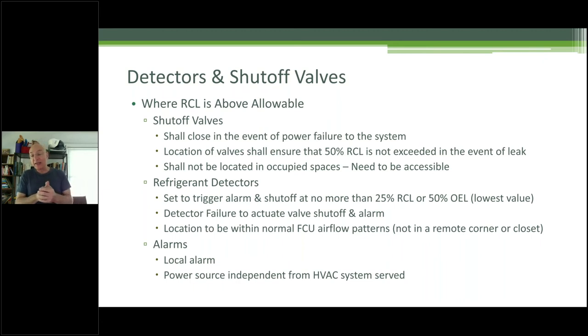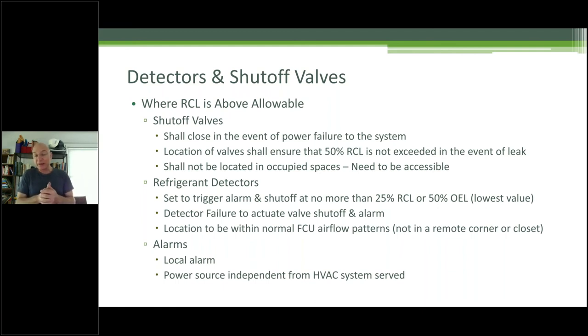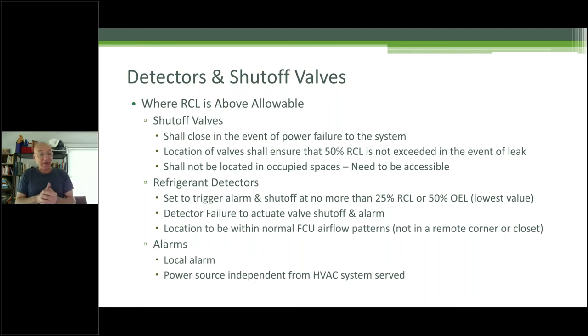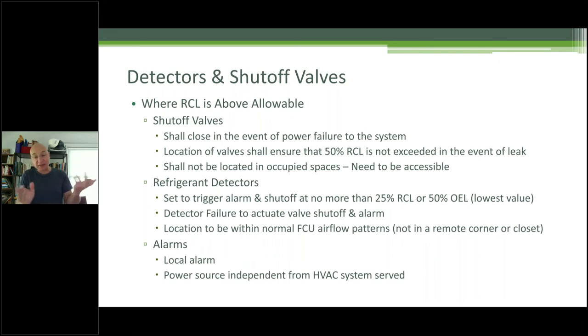Refrigerant detectors are set to trigger alarm and shut off at no more than 25% RCL or 50% OEL — whichever is lowest. OEL is the occupational value; RCL is the refrigerant concentration limit. Detector failure to activate valve shutoff and alarm gets complicated — think about the commissioning of all of them. Location must be within normal FCU airflow patterns — not in a room corner or closet. The power source for the alarm must be independent from the HVAC system served, so not on the same breaker.